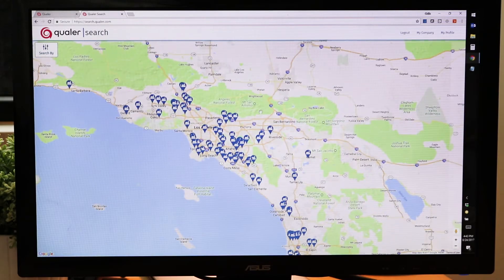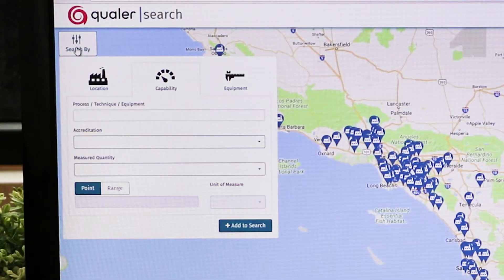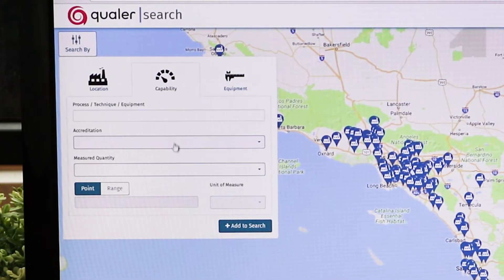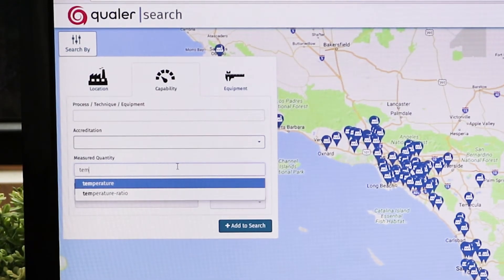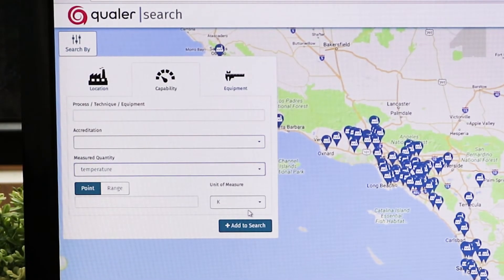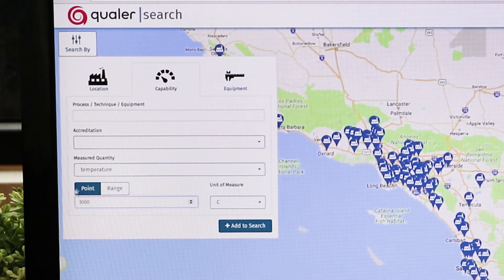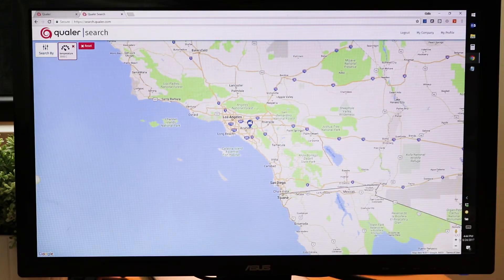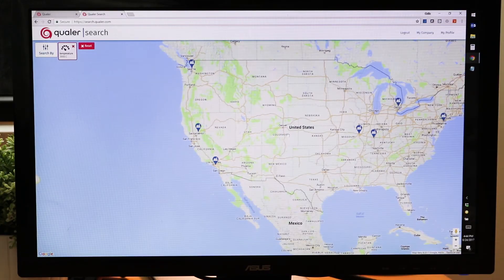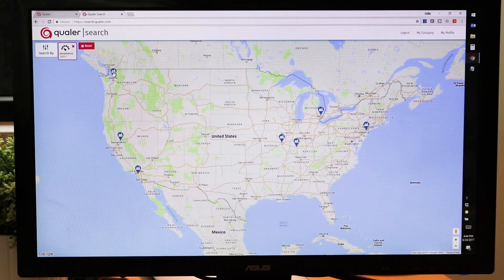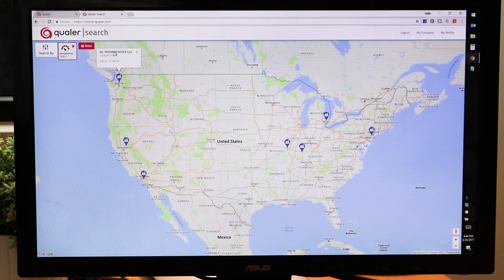Let's take a look at what search can do for us. I'm going to search for a specific parameter. Let's say for example that I have a specialty piece of equipment that has a very high temperature, so I need to calibrate temperature at a really, really hot — let's say 3,000 degrees Celsius. I can enter my point, add it to the search, and Qualer Search is going to instantly filter down to only those calibration labs that have the capability of calibrating at 3,000 degrees Celsius.